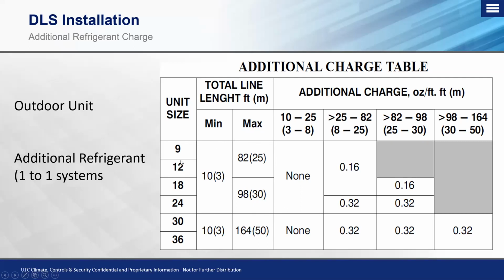So for this example, we're going to use our 12,000. We know our minimum is 10 foot. We've met that. We know our maximum is 82 foot. We're not over that. 10, which is the minimum, to 25 feet, which is the basis of that factory charge in the outdoor unit. No additional refrigerant charge. So if we ran 18 feet, we don't have to do any additional refrigerant charge. We can crack open our service valves and test fire the system.